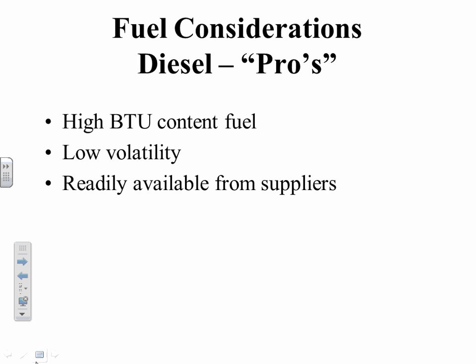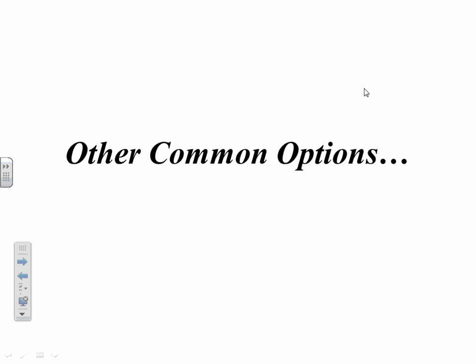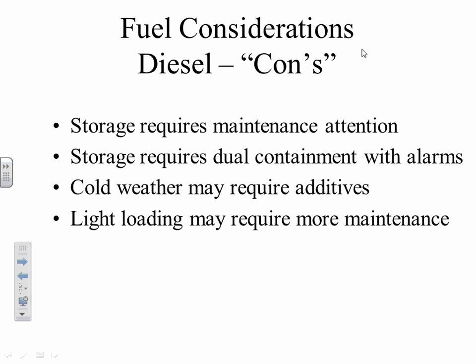Fuel considerations for diesels. On the positive side, it's got a very high BTU fuel content. I think it's like 140,000 per gallon or something like that. Low volatility. Won't see a lot of fires with diesel fuel. It might get real slippery with a diesel fuel leak, I should say. And it's readily available from suppliers. On the con side, the storage does require some maintenance attention. If you don't use all the fuel, you might need that fuel cleaned because you're going to get a bio thing happening in the tank where things are going to start to grow over time if it sits too long. And I'm talking over a year's time.